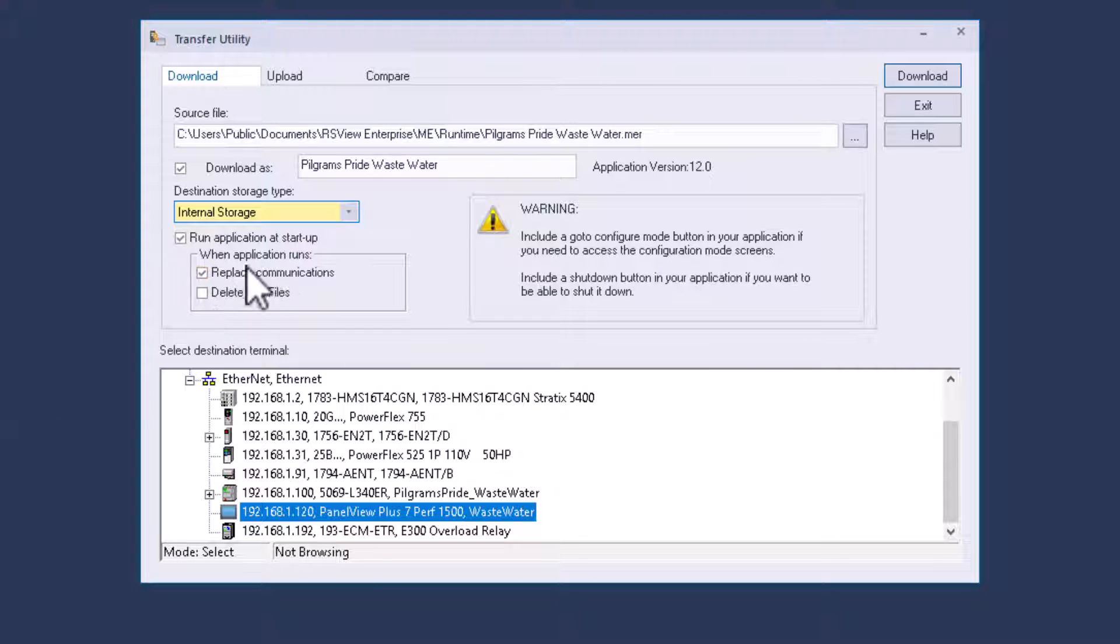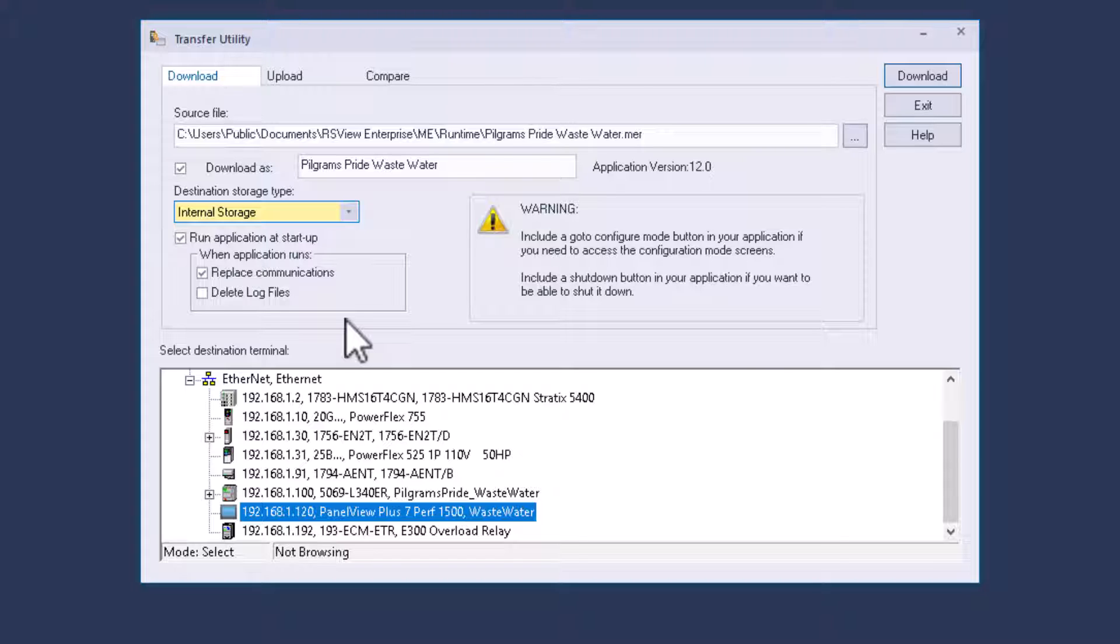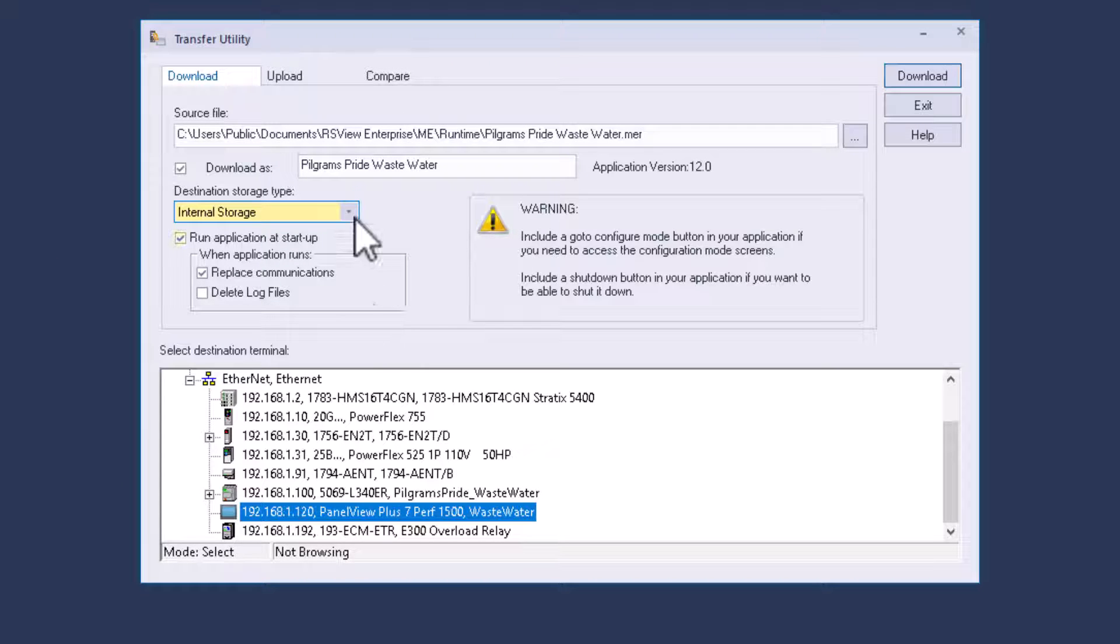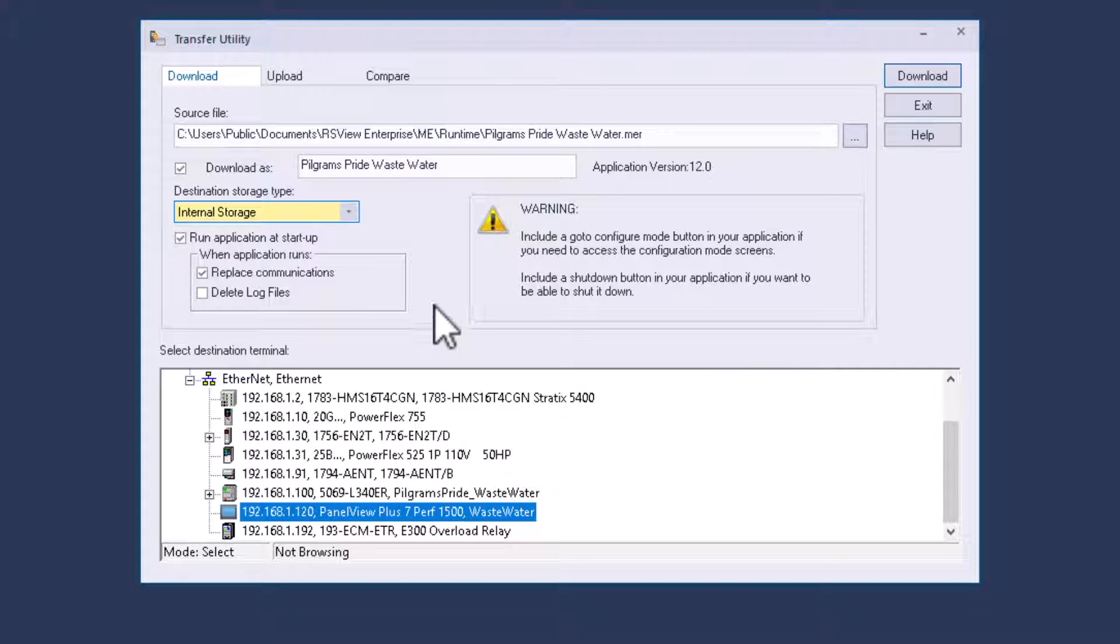If you're unsure about that, do not replace communications, but if it is a brand new panel view plus or a panel view or a panel view performance, then you do have to replace the communications because it's going to replace the communications that you built in the design of the HMI. It's going to replace them with, and that's going to be the connectivity path that the actual HMI, the operator interface uses to go back and talk back to your PLC. Hopefully that made sense on that.